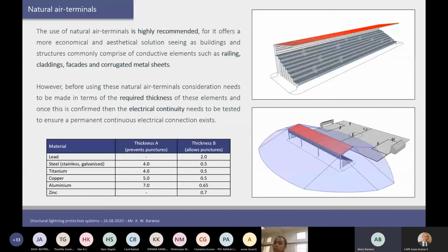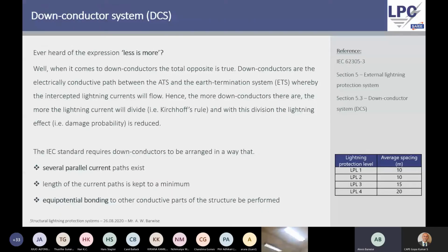So moving on, we have now learned how to catch the lightning, so intercept it via the air termination system. Now we have to safely and controllably conduct the lightning currents down to Earth. I use this because I believe it's the best way to remember it. I think everyone has heard the expression sometimes in business that less is more. And in down conductors, it's exactly the opposite. In down conductor systems, you want to have as many paths as possible from the roof all the way down to the Earth itself.